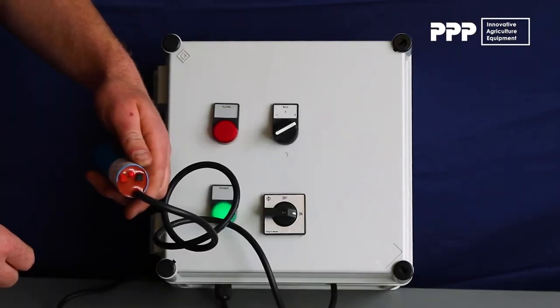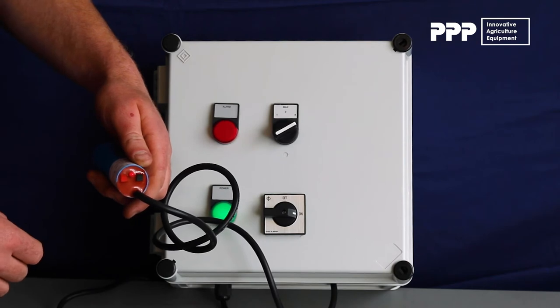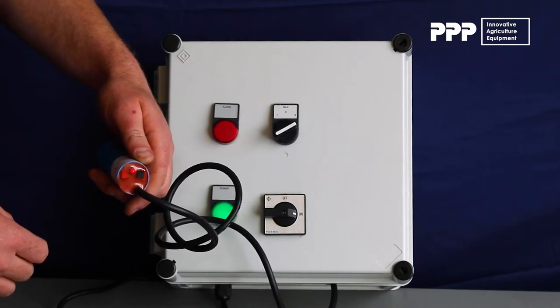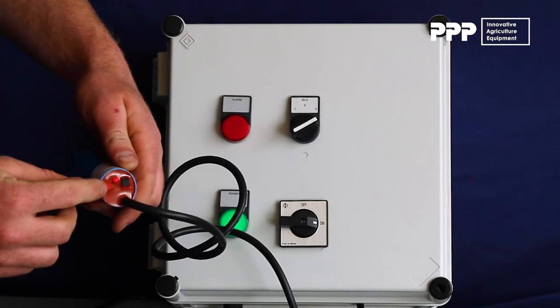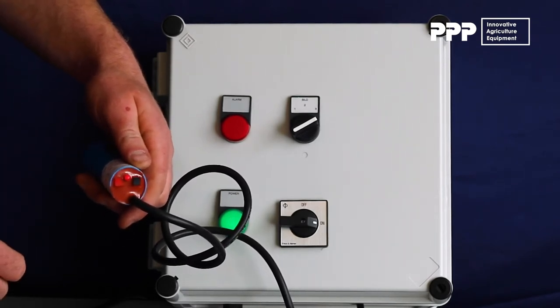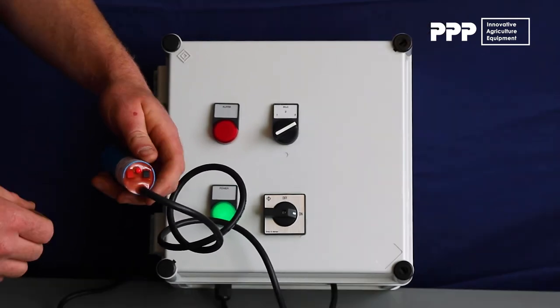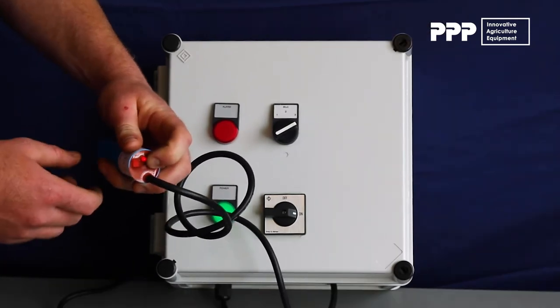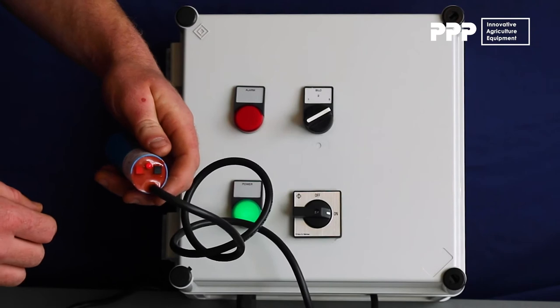Silo vibrators don't need any delays so to cancel out all delays you must set it to zero seconds. You can do this by pushing the red button until the LED strobes once. This will zero out the minutes. To zero out the seconds you must push the black button until the LED strobes once and this will zero out the seconds.